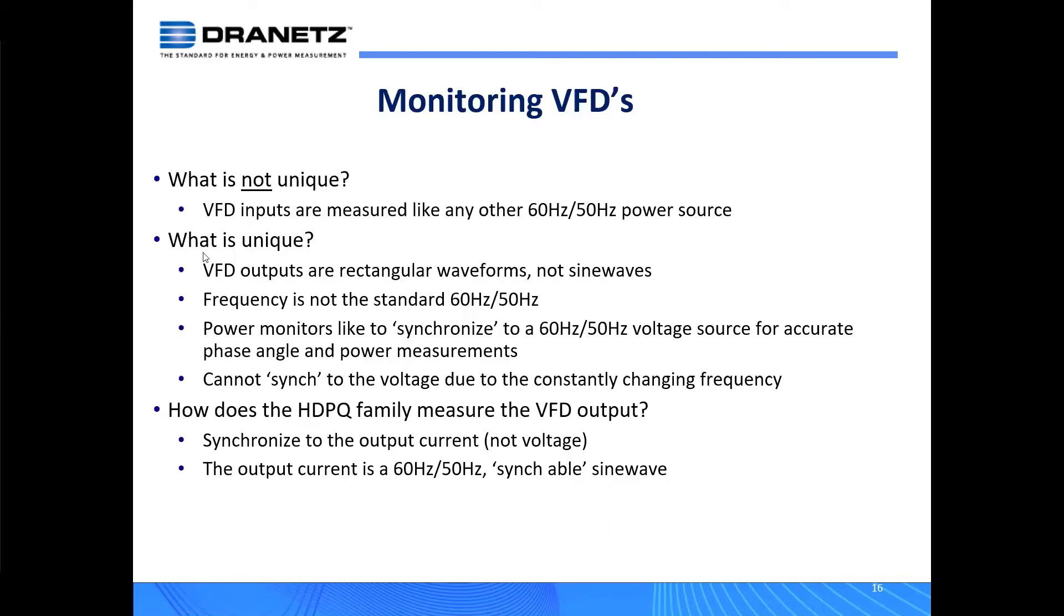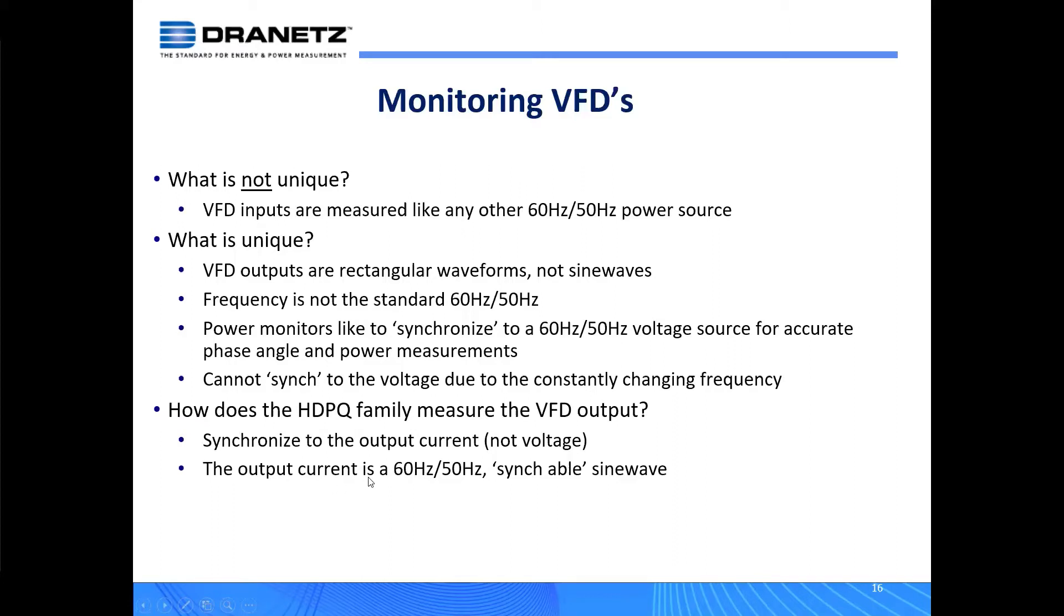A traditional power meter can't sync to the voltage due to that constantly changing frequency. So how does the HDPQ family do this? The answer is quite simple: you synchronize to the output current, not the output voltage, because the voltage is changing. The current is a very stable or fairly stable 60 or 50 hertz sine wave, so it's what we call a syncable sine wave. That means we can get the instrument to synchronize on that to produce accurate measurements.